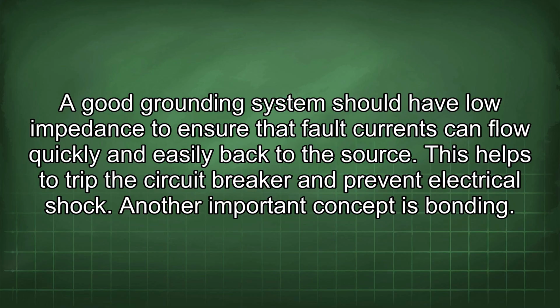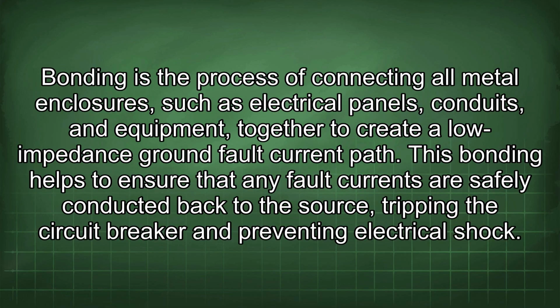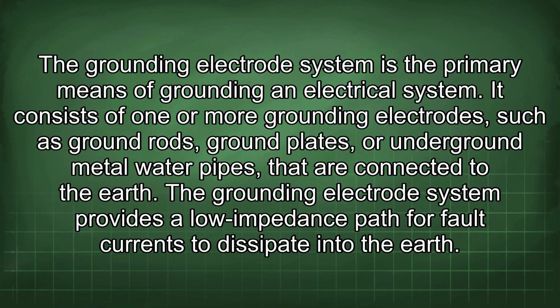Another important concept is bonding. Bonding is the process of connecting all metal enclosures, such as electrical panels, conduits, and equipment, together to create a low impedance ground fault current path. This bonding helps to ensure that any fault currents are safely conducted back to the source, tripping the circuit breaker and preventing electrical shock.